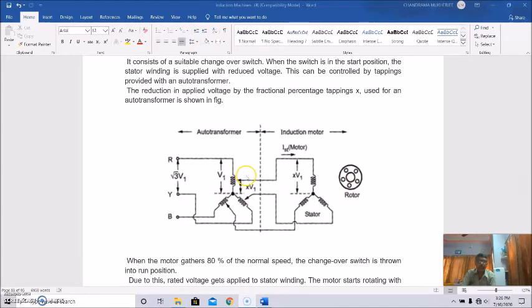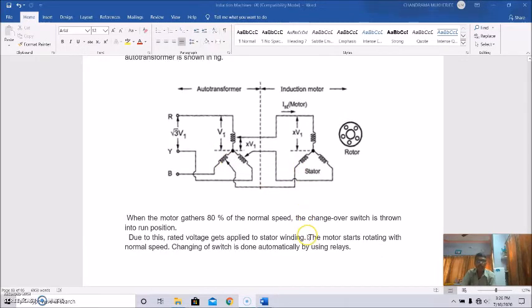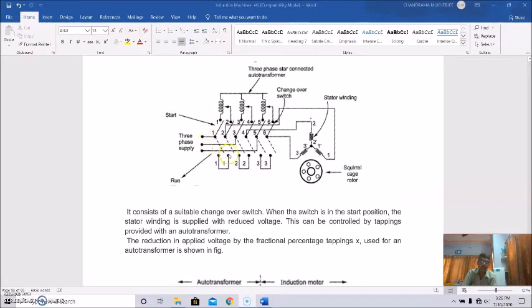This is the star connected terminal of the auto transformer. This is the supply voltage, root 3 V1 is the line voltage, and this is the per phase voltage. These are the different tappings of the auto transformer connected to the stator winding terminals. When the motor gathers 80% of its normal speed, the changeover switch is thrown into the run position. This is the changeover switch, and it is right here in the run position.